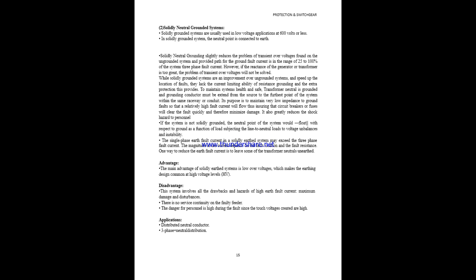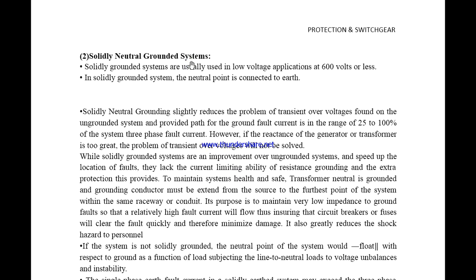And next we are considering solid neutral grounding. It is nothing but connecting a plain conductor from the neutral point to the earth without any component. Through solid neutral grounding, the problem of transient overvoltages is slightly reduced. That is, when compared to the ungrounded system, it is better, and it provides a path for the ground fault current in the range of 25 to 100% of the system three-phase fault current. However, if the reactance of the generator or transformer is too great, the problem of transient overvoltages will not be solved. Solidly grounded systems are an improvement over ungrounded systems, and their speed of fault location is better.